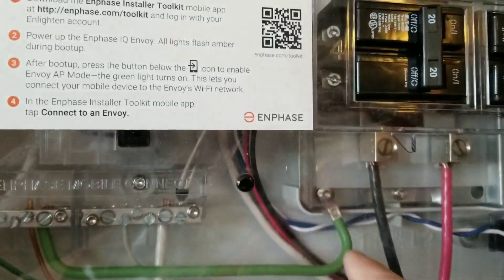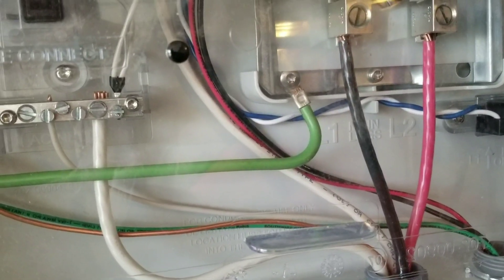Which is incorrectly installed — it's just going to read the same thing. So this white wire back here comes up and goes in there, but that runs back to the main panel. I'll take you back there and show you how the consumption CTs are installed.